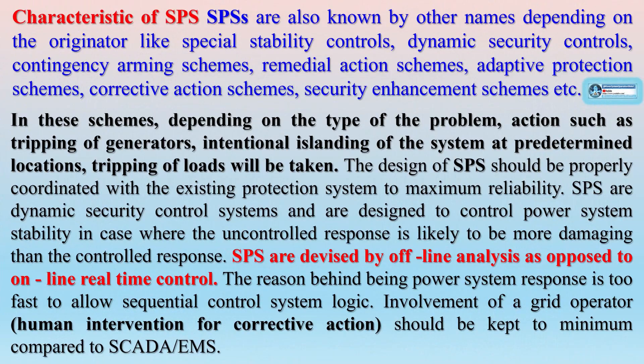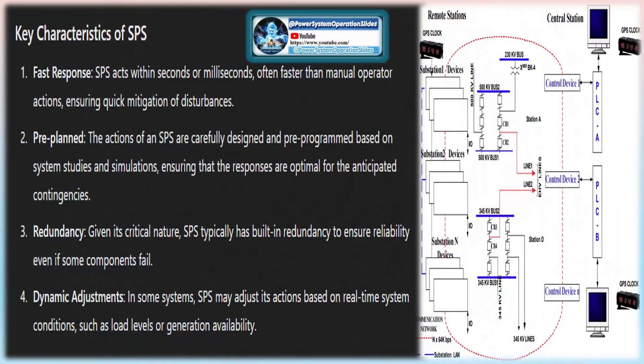SPS are devised by offline analysis as opposed to online real-time control, because the power system response is too fast to allow sequential control system logic. Involvement of a grid operator's human intervention for corrective action should be kept to a minimum compared to SCADA EMS. In certain cases, SPSs can be designed for detection of system conditions resulting in overloading, voltage collapse leading to instability, disconnection of single or multiple lines, generator tripping, increased HVDC power transfer capability, or premeditated load shedding.